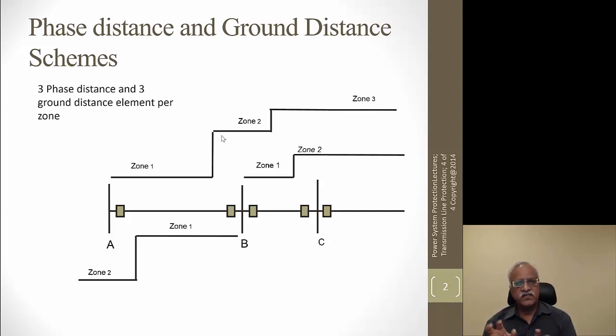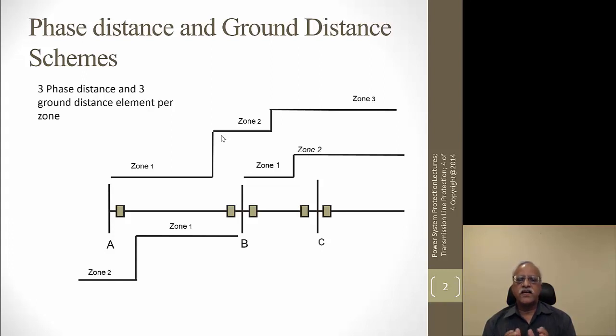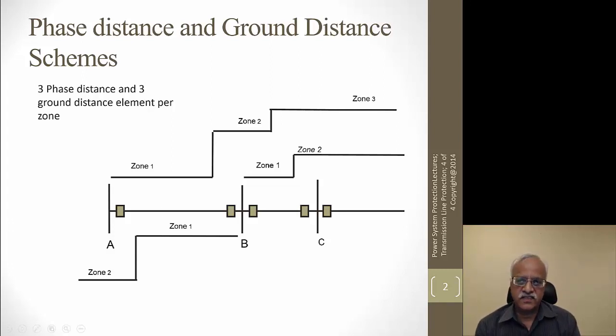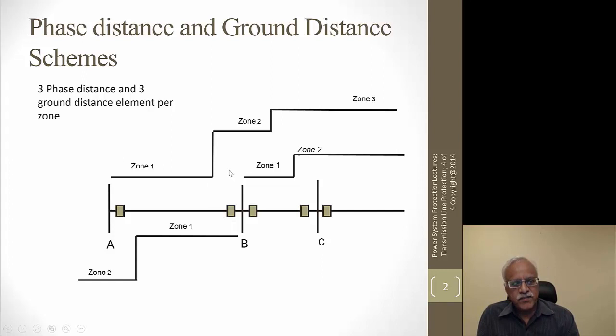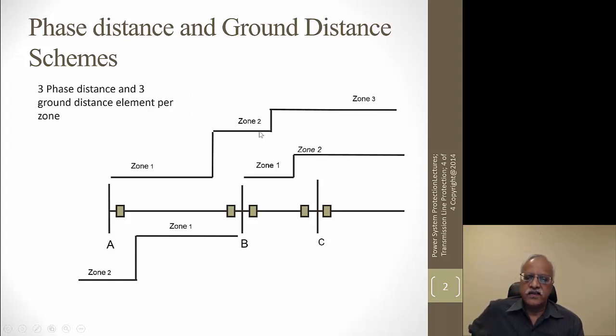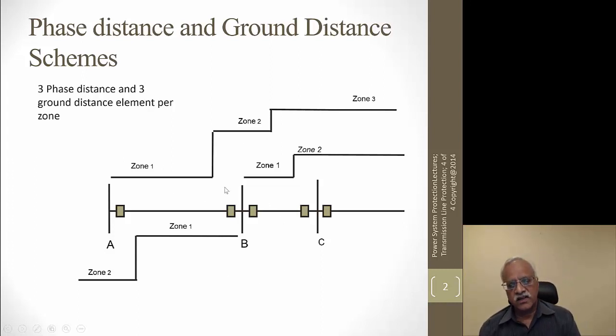Each of those has three elements within them, giving six elements detecting faults on that particular line. Zone 1 is allowed to operate if the fault is within 85% of the line section. Zone 2 is time-delayed to allow discrimination for faults in the adjacent line section, delayed by 15 to 25 cycles based on the utility's coordination margins. Zone 3 can also be used to provide complete redundancy for all lines going out of section B.